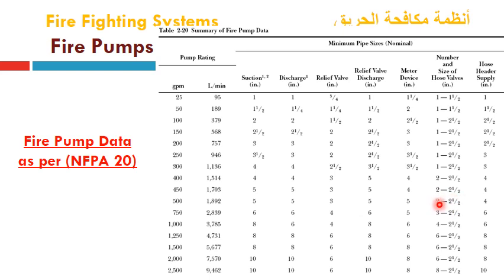Two hose valves can be used, each with 250 GPM, to cover the 500 GPM rating of this pump, and each one has a size of 2.5 inch. The number of hose header supplies that can be used is 4. Here, it is used with 125 GPM per hose header inch, and the diameter of this header, which will carry the flow of these two 2.5 hose valves, is 4 inch.